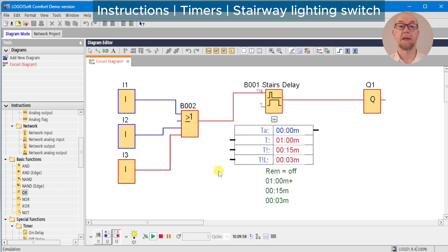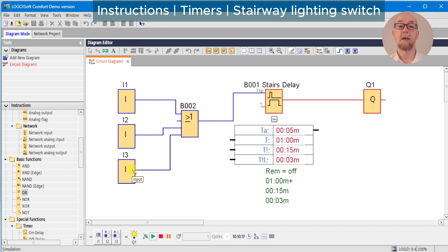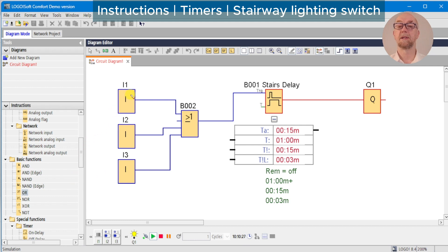The disadvantage of this OR gate arrangement is that we've now used three inputs, and obviously for a multi-story building this would add up. The LOGO has a limited number of inputs, although expansion modules can be used. In a practical situation you'll probably just wire all the physical switches in parallel to one input on the LOGO.